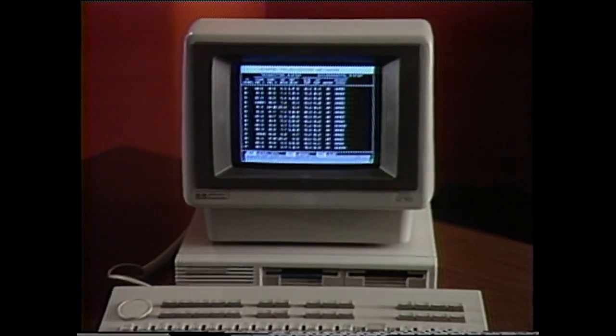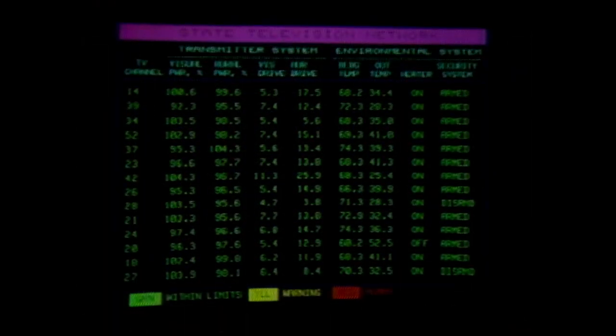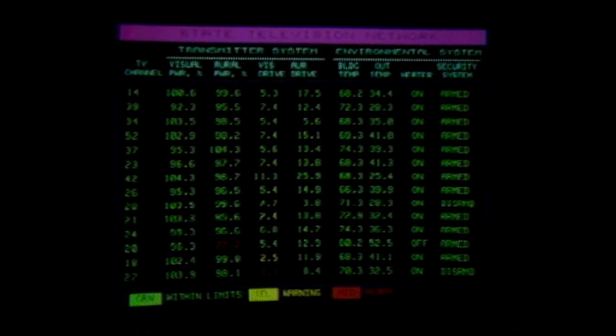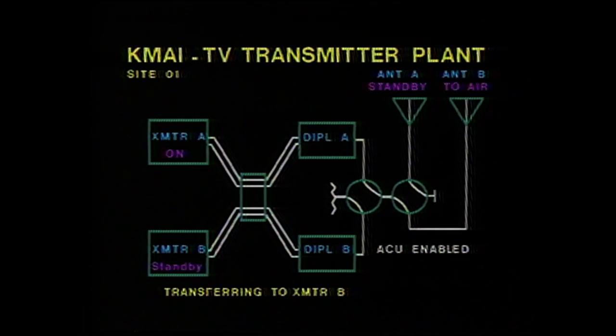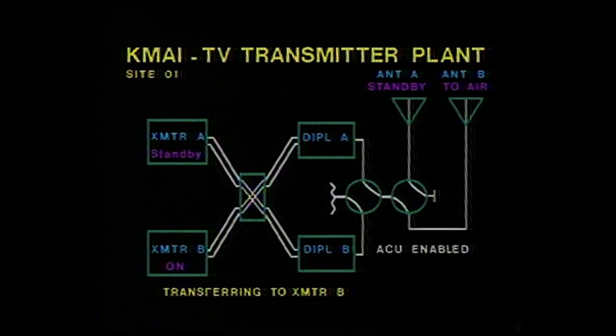Let's see how the ACU-1 performs. In this demonstration, the ACU-1 monitors output power control. When yellow limits of first stage warning are reached, output power is corrected. Nuisance overloads may be reset automatically for a predetermined number of times. The system will then initiate the transfer to an auxiliary transmitter, complete with the appropriate time delays for filament warm-up and antenna switching. This switchover may also be initiated manually.